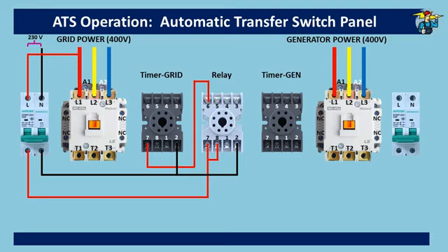Now, connect port 7 to the common port 8, thereby, after the set time delay on the grid timer, outlet port 6 gets power. All we need now is to connect number 6 of the grid timer to the grid contactor operating coil A1.